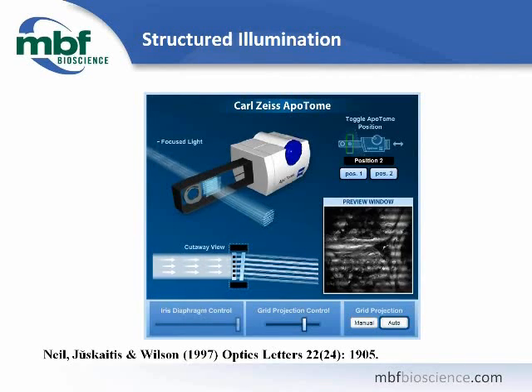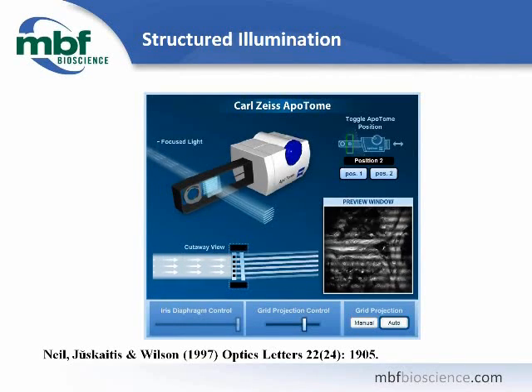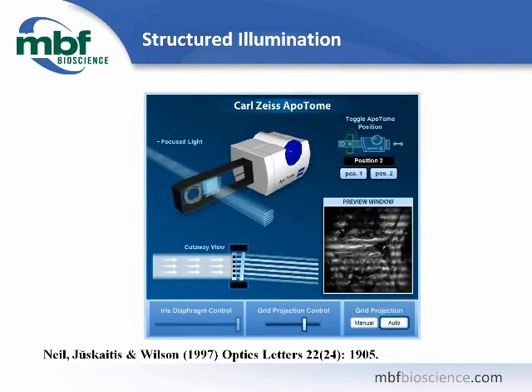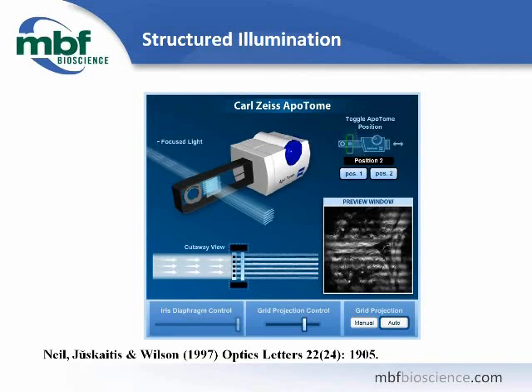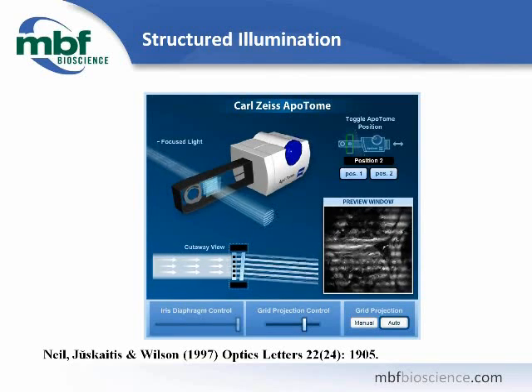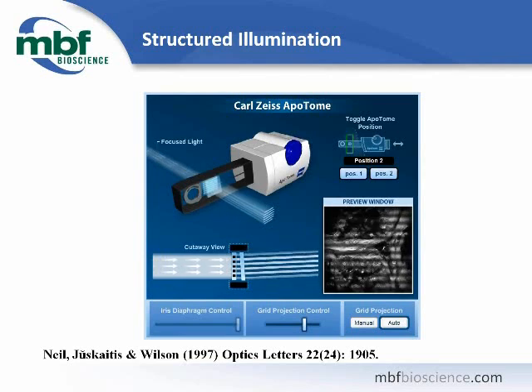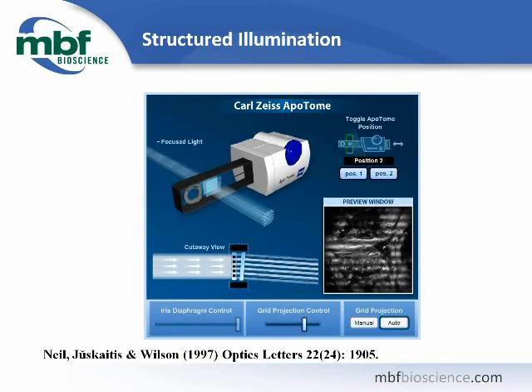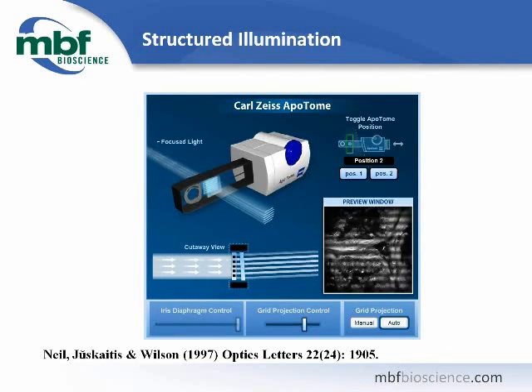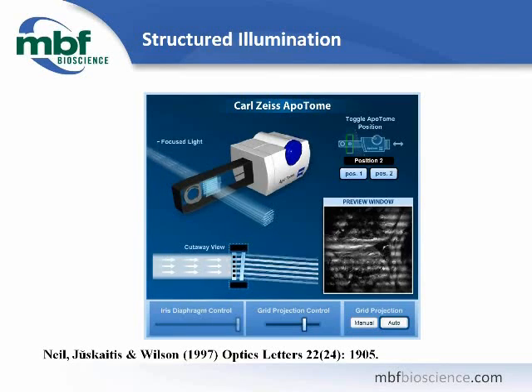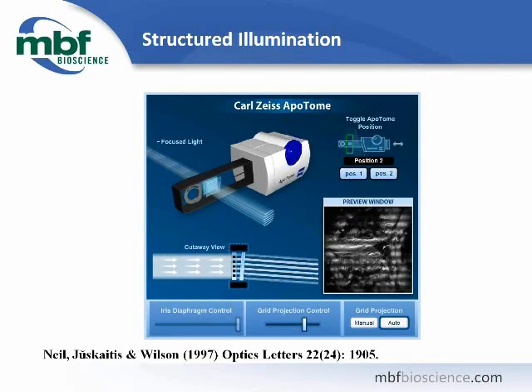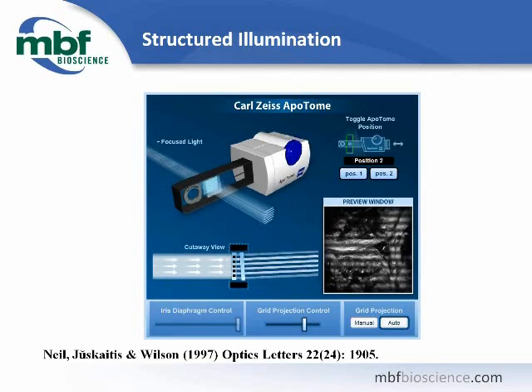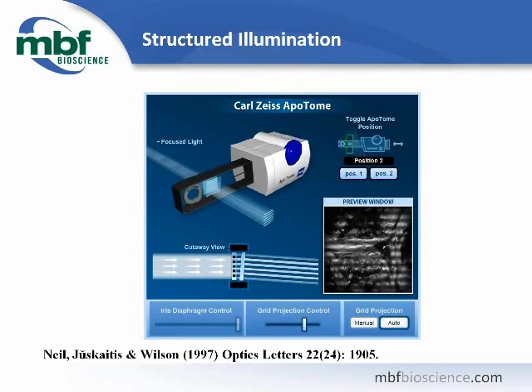You switch between the two positions by physically moving the slider. In position 1, the slider is partially out of the F-slot. In position 2 for ApoTome mode, the slider is fully inserted. You will hear a beep when the ApoTome is in place. When the ApoTome is in position 2, you will see the grid pattern wobbling. This helps keep bleaching of the sample even to reduce the risk of residual grid lines in your ApoTome images.